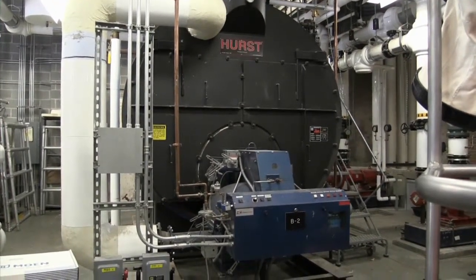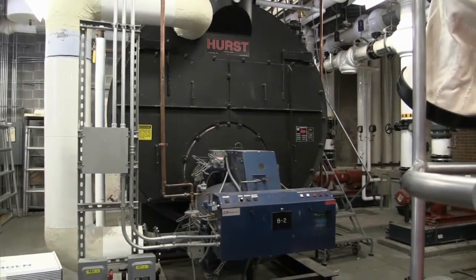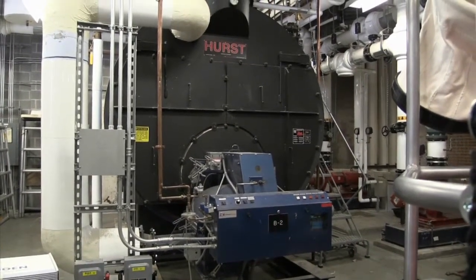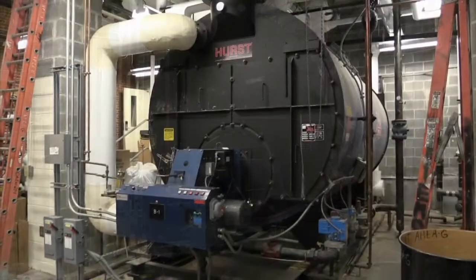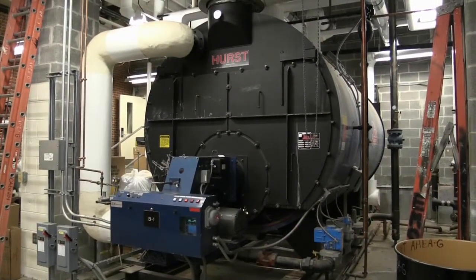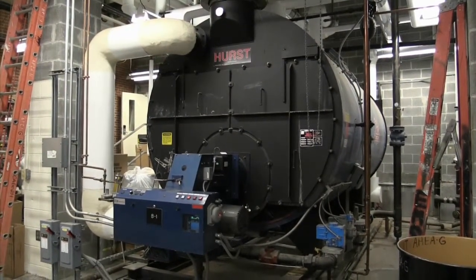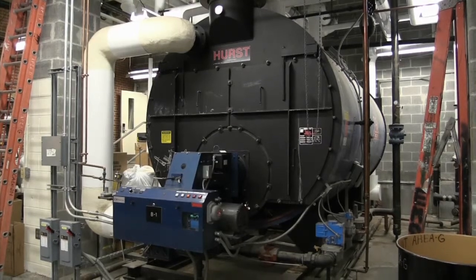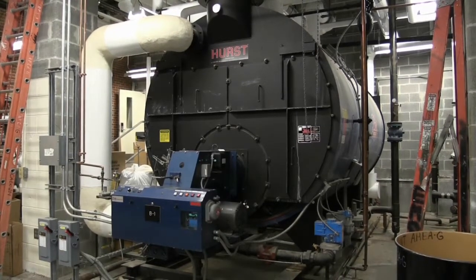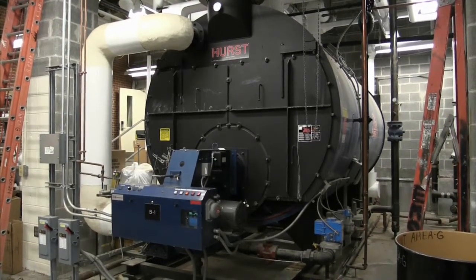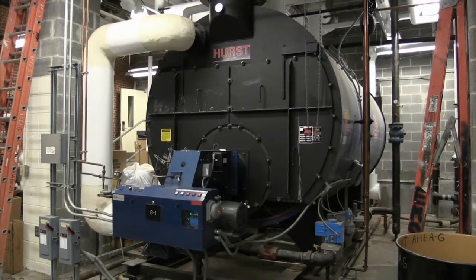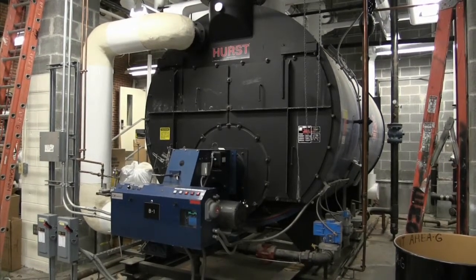Observed building automation system trended data indicates that the differential pressure set point was set at 20 pounds per square inch. For a closed-loop system, a differential pressure set point of 20 psi is too high for summer conditions. This should be lowered for summer and warm weather operations to no greater than 10 psi.